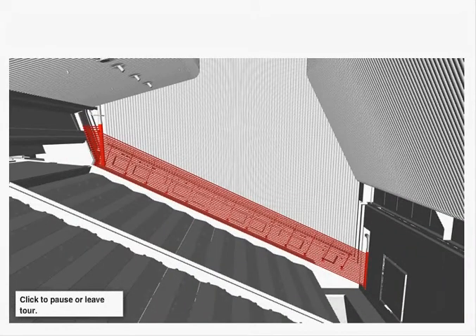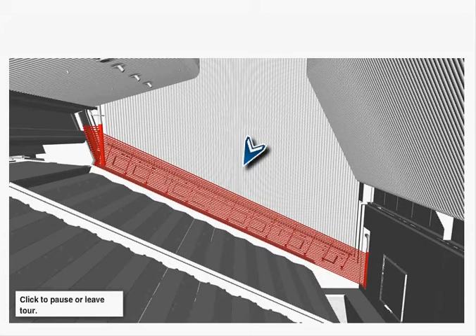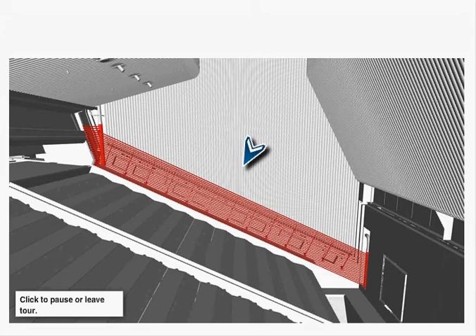Unlike many of our competitors, our waste to energy plants are equipped with water cooled wear zones. The water cooled wear zone ensures long life of the plant and minimizes the downtime from unplanned stoppages. The maintenance cost is extremely low compared to refractory. What's more, the higher heat uptake will result in a more compact boiler. Finally, the water cooled wear zone is part of the boiler circulation system and doesn't require extra process equipment.